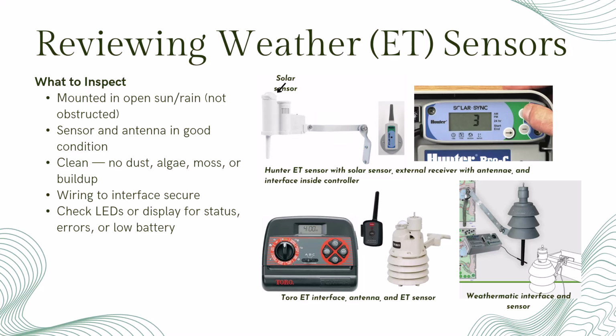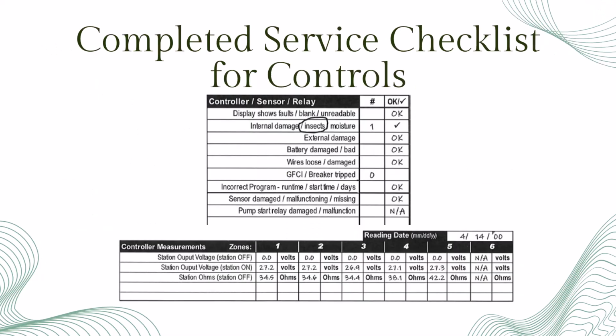Make sure the sensor is mounted in the open, not under an eave or tree, and that it isn't damaged or covered in pollen, algae, or debris. Check the wiring at the interface and inspect the antenna, whether it's internal or external. Finally, verify communication by checking the LEDs or the controller display for icons, warnings, or low battery indicators. If the sensor can't communicate, the controller can't self-adjust.